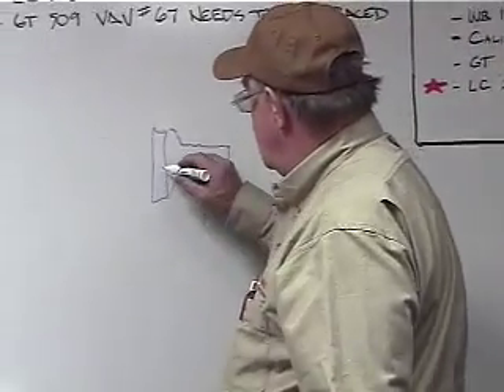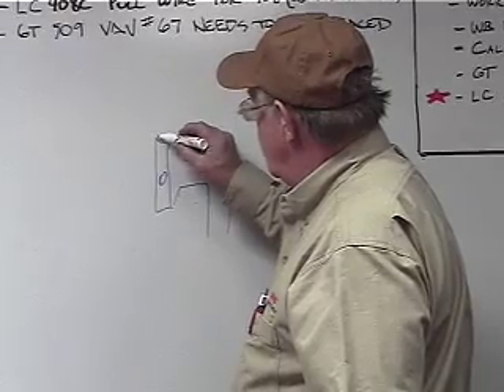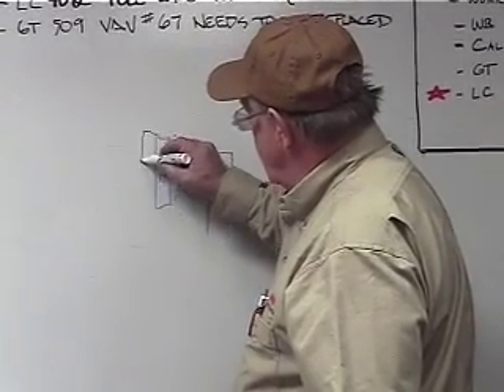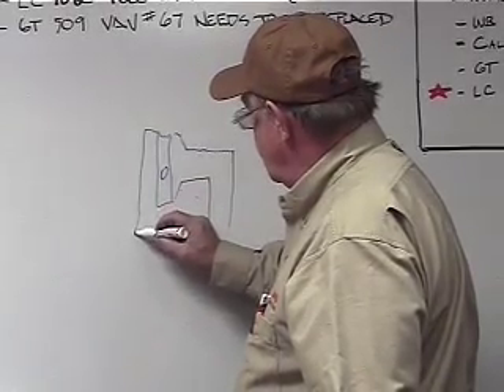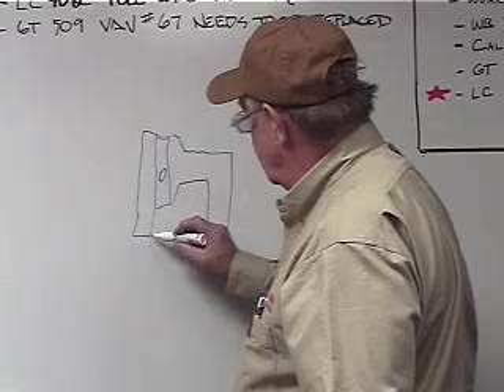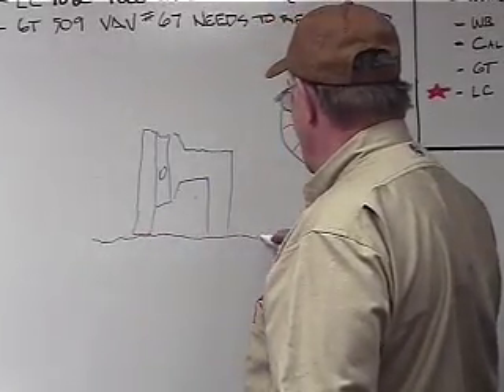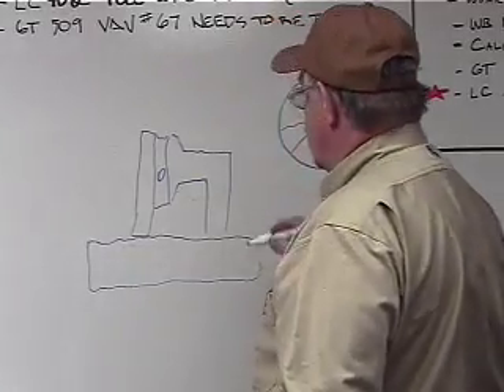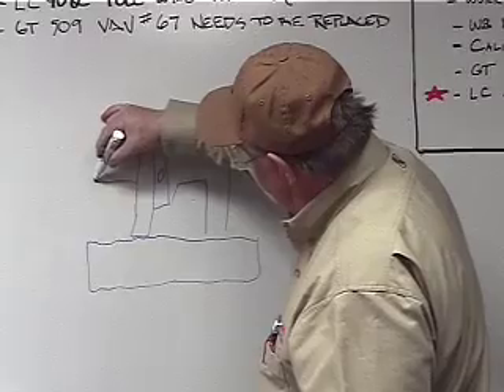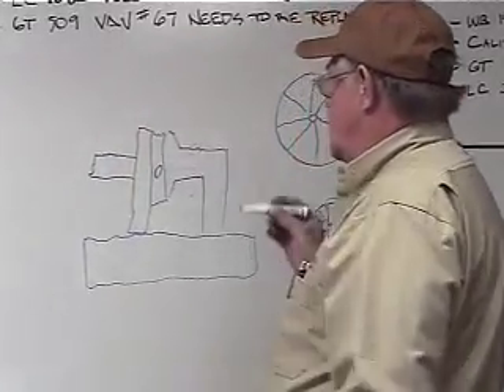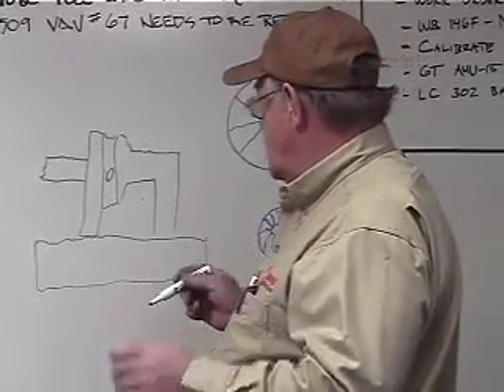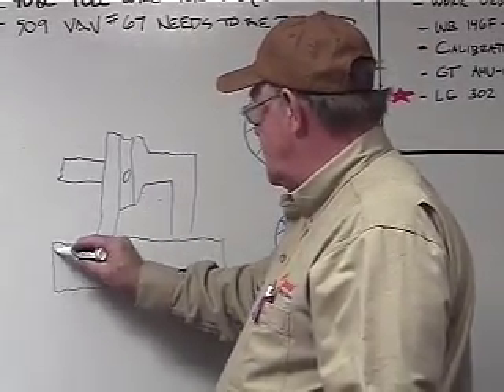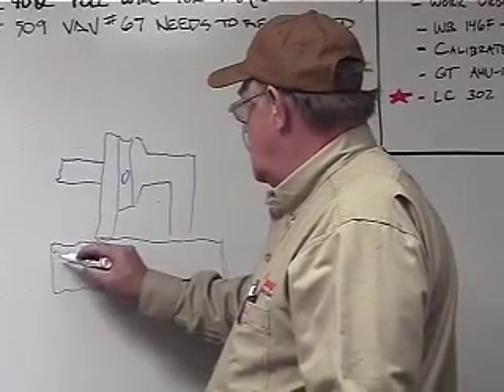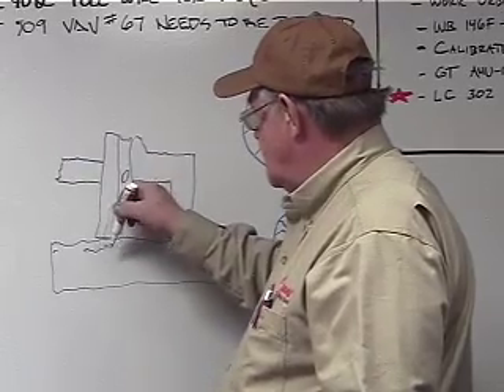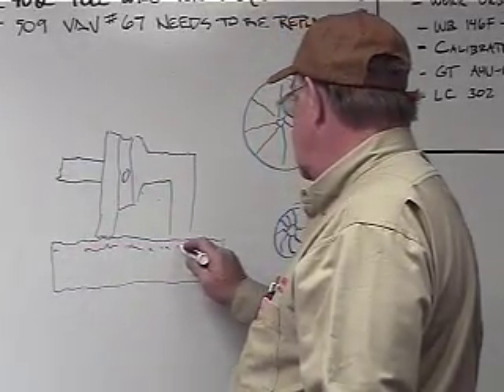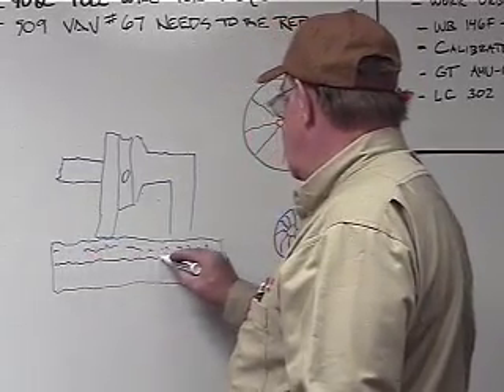As it comes out, we're going to go into another thing that is actually a discharge volute that comes into your condenser, and your compressor is going to be right here. Okay, so what we're doing is we're compressing the gas into a high pressure gas, and this high pressure gas goes into your condenser, and there's going to be a little plate here so that all the refrigerant just doesn't hit the top of the tubes right here, but it sends all your gas, high pressure gas, down over these tubes.